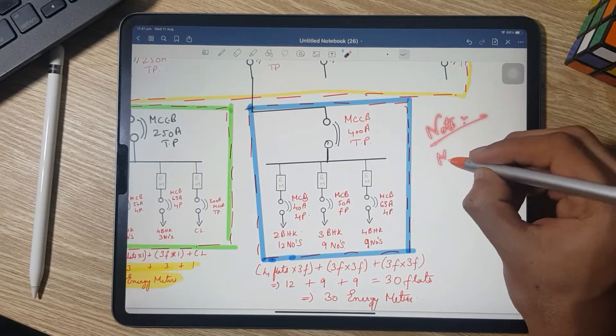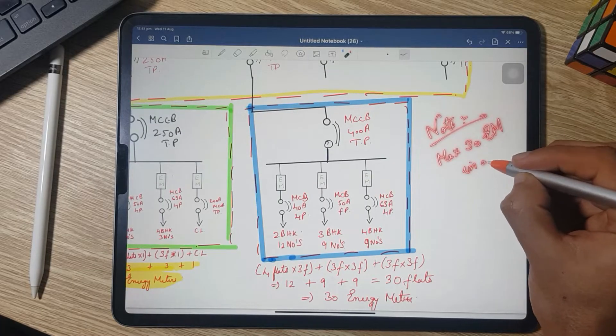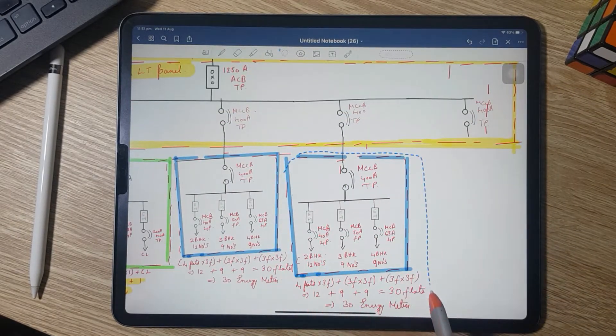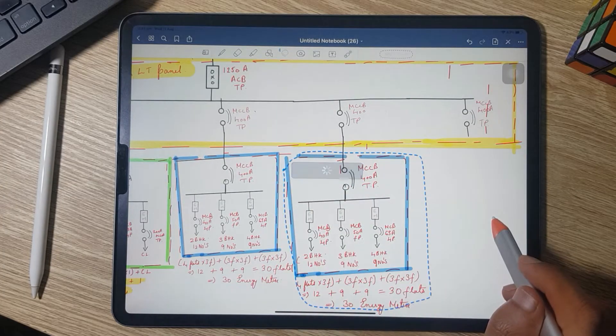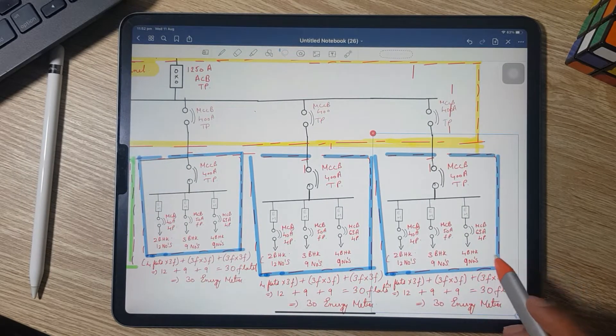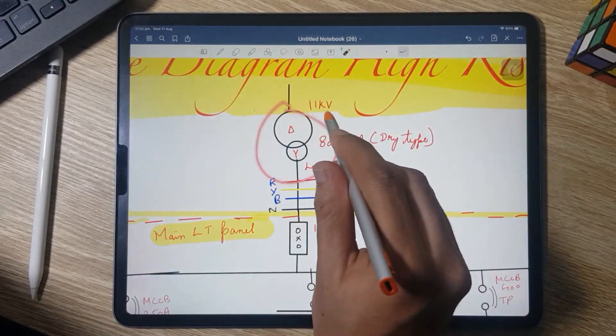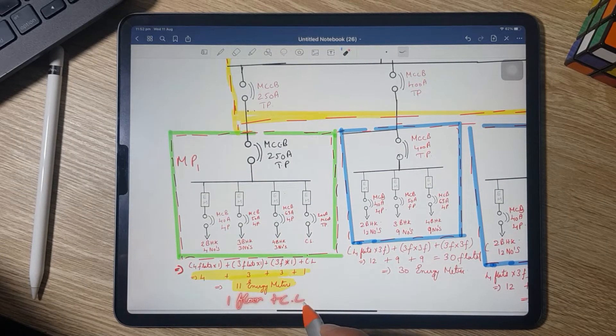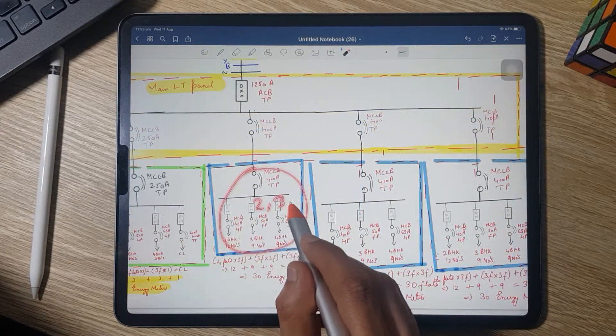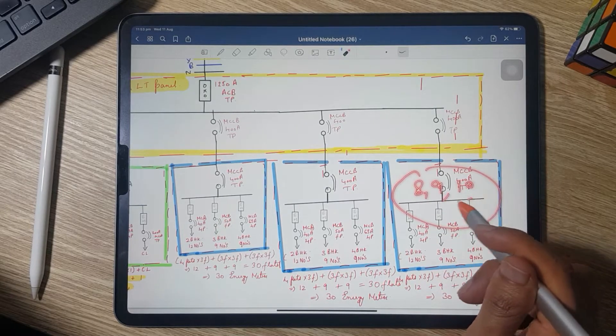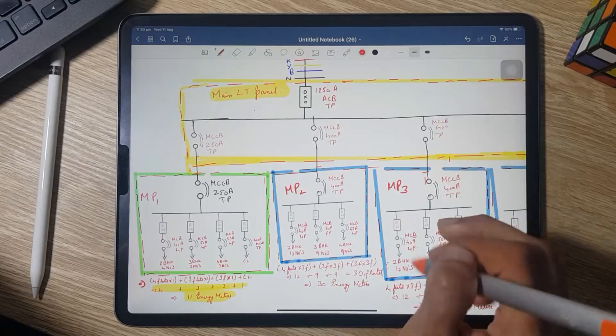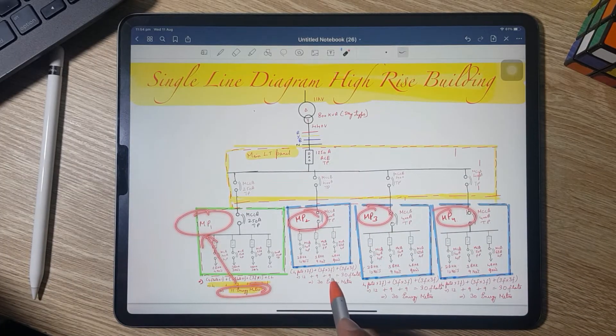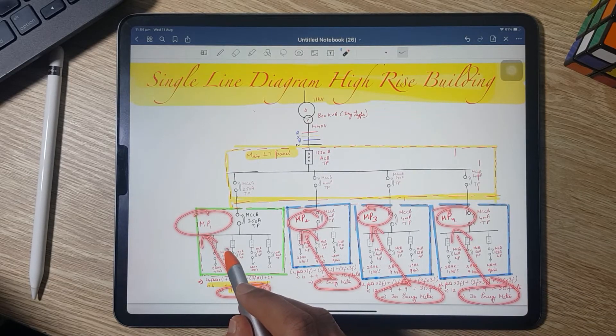The key difference in high-rise building design is the 30 energy meter limit per panel. Meter Panel 3 covers floors 5–7 and Meter Panel 4 covers floors 8–10, each with a 400 A triple-pole MCCB and 30 energy meters. Final summary: 800 kVA transformer → main LT panel → Meter Panel 1 (11 meters, first floor + common load) → Meter Panel 2 (30 meters, floors 2–4) → Meter Panel 3 (30 meters, floors 5–7) → Meter Panel 4 (30 meters, floors 8–10).